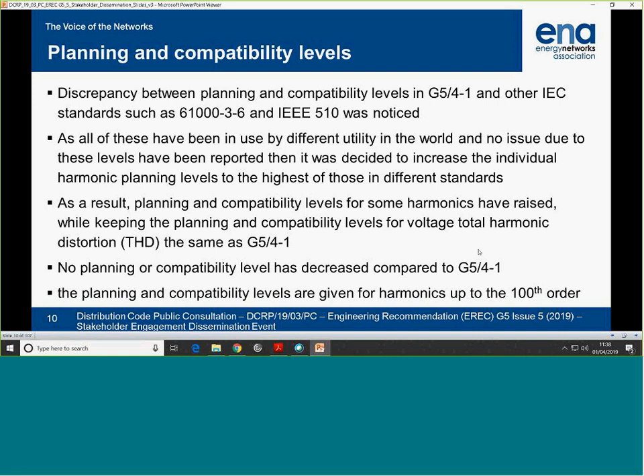Plan compatibility levels. What we did was we looked at these planning and compatibility levels in use in UK, and also in IEC and IEEE, which North American use and South American use, mostly. We know that there are discrepancies. Some harmonics in one standard is higher than what we use here, or vice versa. So we say, okay, these have been in use for many years, and nothing has been reported that they're causing problem or damage to equipment. Why not use all of them? And this is what we did.